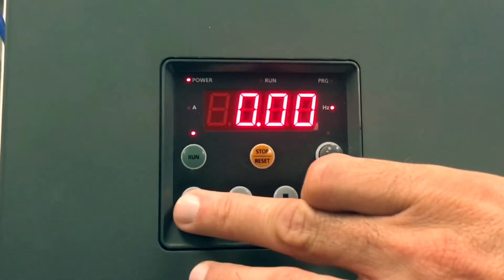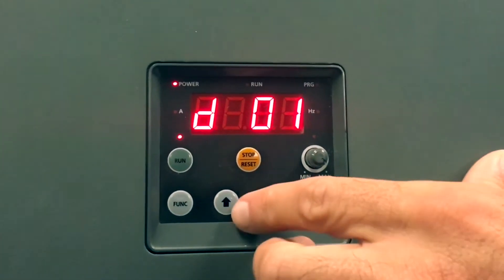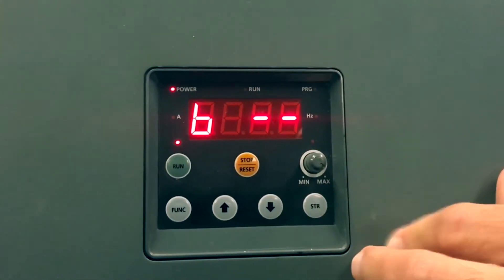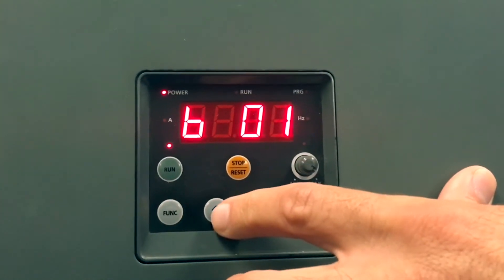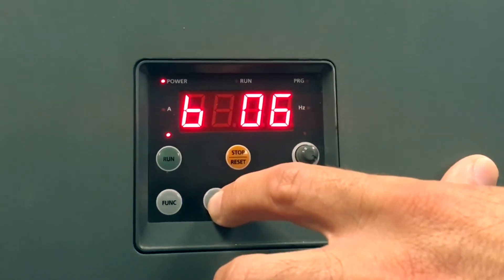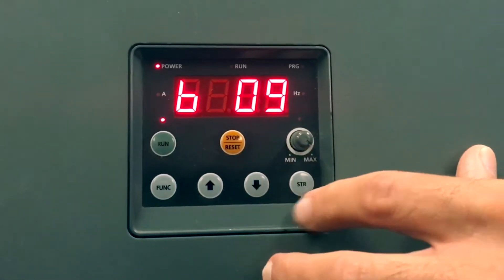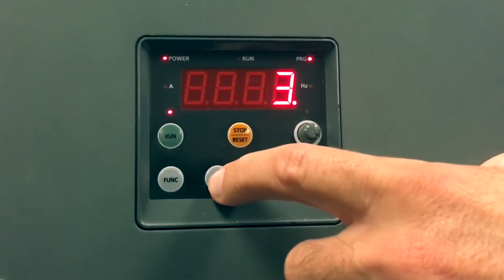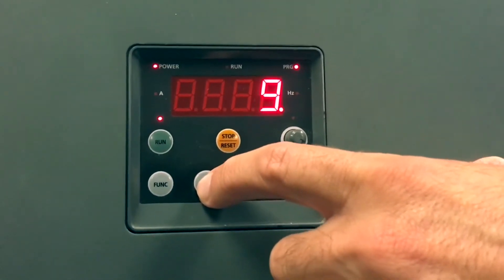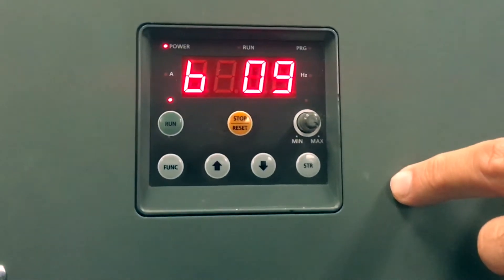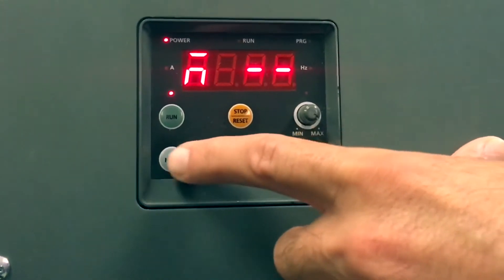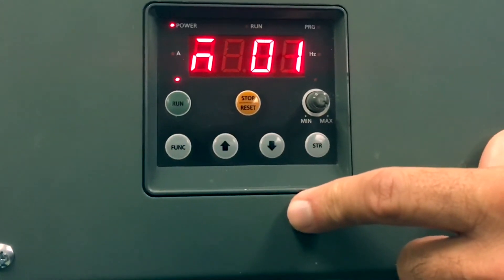In order to do this we must access our M parameters. Go to B09 first, set the value to 11, then press store. Now push function which will bring you to B dash dash. Simply click the up arrow to access M parameters.